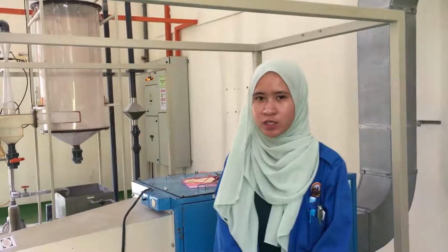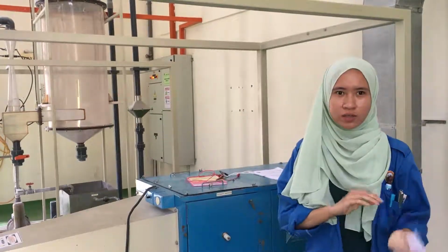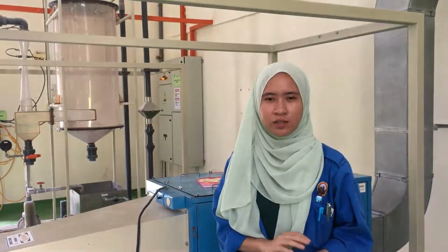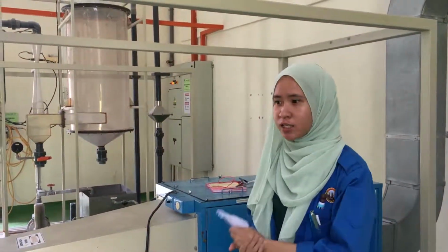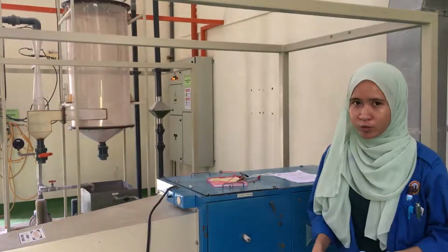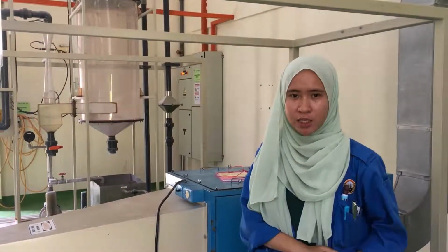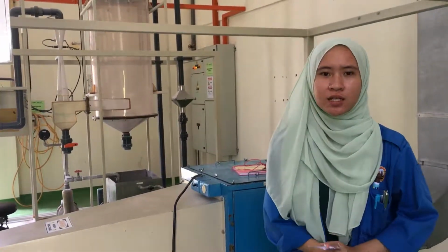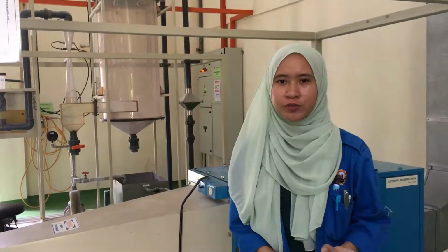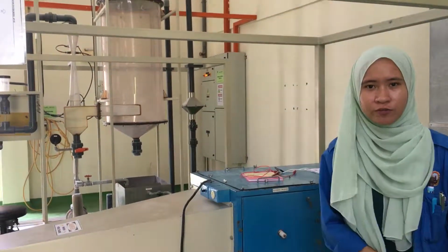There are four recommendations that can be made to improve the efficiency of the ESP unit. The first one is that corona blocking may occur under high dust concentration, so a pre-dusting facility is necessary. Secondly, gas humidity has a significant effect on the ESP performance. Water spraying can improve this, especially under conditions where high dust resistivity occurs. Thirdly, an acoustic wave dust cleaning mode should be available. It can improve the ESP collecting performance effectively and economically.